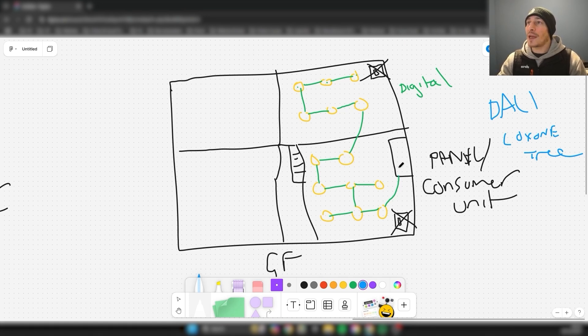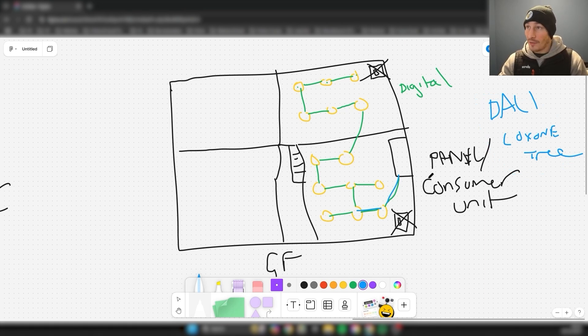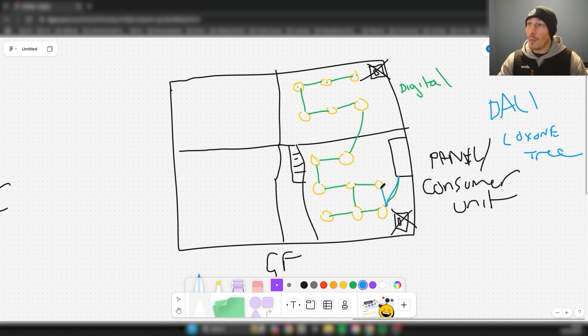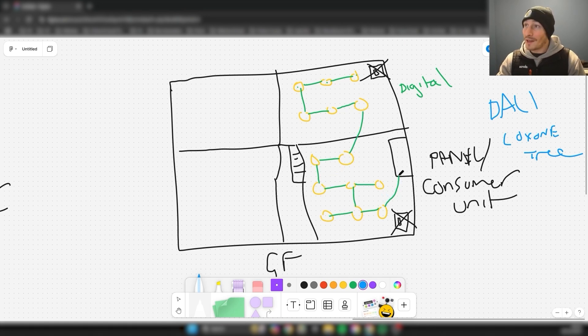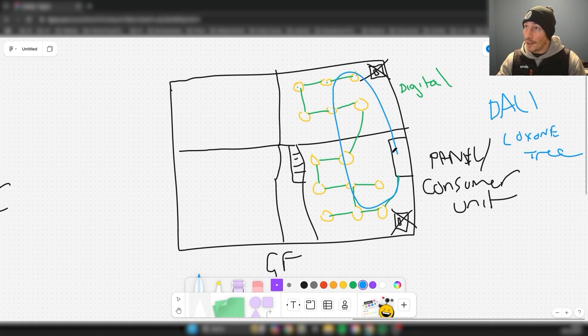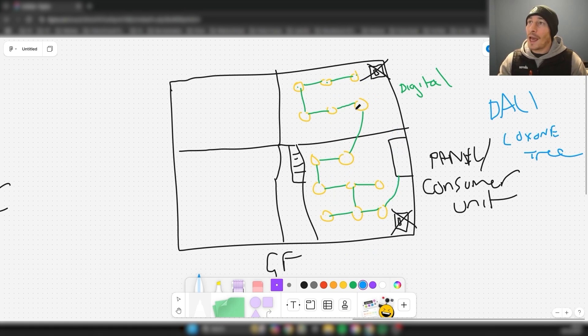One, you can pretty much wire it however you like. It will depend on the system so you need to check that first, but you can pretty much wire it in whatever topology you like, providing that there's not a ring. There's no ring and you've got both ends terminated because that never works when you've got a terminated ring.